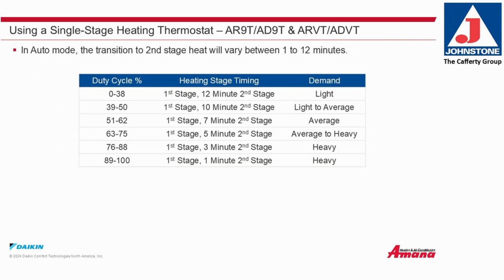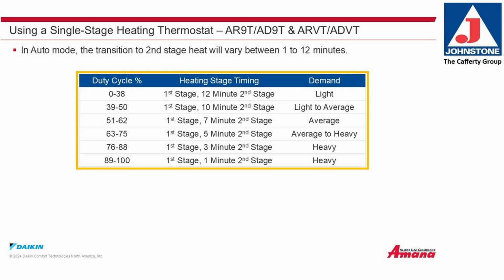Using a single-stage heating thermostat, in auto mode, the transition to second stage heat will vary between 1 and 12 minutes. See the chart below showing the duty cycle percentage, heat stage timing, and the demand.